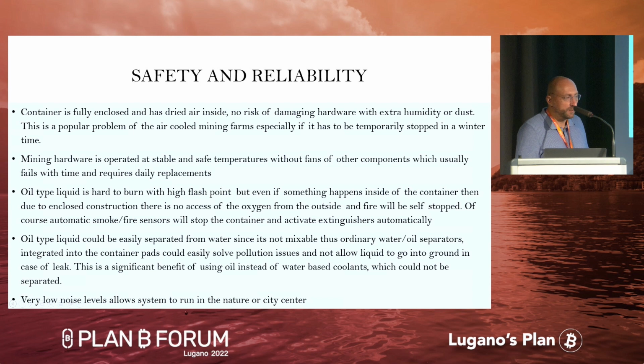People think oil is really dangerous. Of course it can burn, but there are a number of oils available on the market, and we can choose the best one with a very high flash point. Since our container is completely enclosed, there's no access to oxygen inside, so even in case of a short circuit, where a cable starts to burn, that oil will never burn. Of course we have an alarm and fire extinguisher system that can trigger immediately and switch off the container, but even if nothing of that worked and there was an open fire, it would just die by itself, because there's no oxygen to support it.